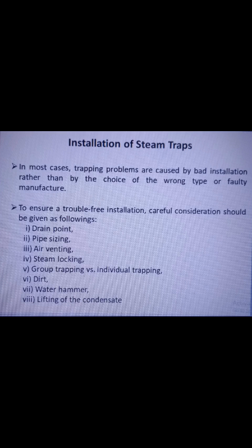This is not always appreciated. For example, it is useless to provide a 15 mm drain hole in the bottom of a 150 mm steam main, because most of the condensate will be carried away by the steam velocity. A proper pocket at the lowest part of the pipeline, into which the condensate can drop, of at least 100 mm diameter is needed in such cases.